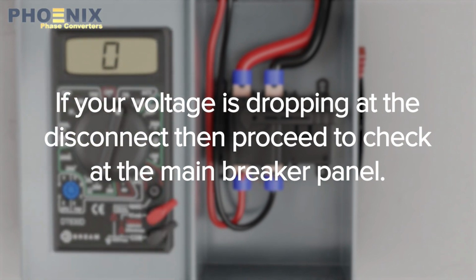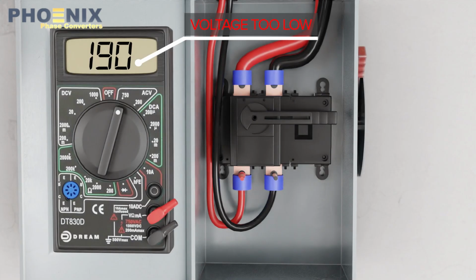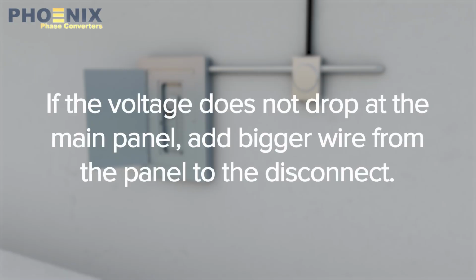If your voltage is dropping at the disconnect, then proceed to check at the main breaker panel. If the voltage does not drop at the main panel, add bigger wire from the panel to the disconnect.